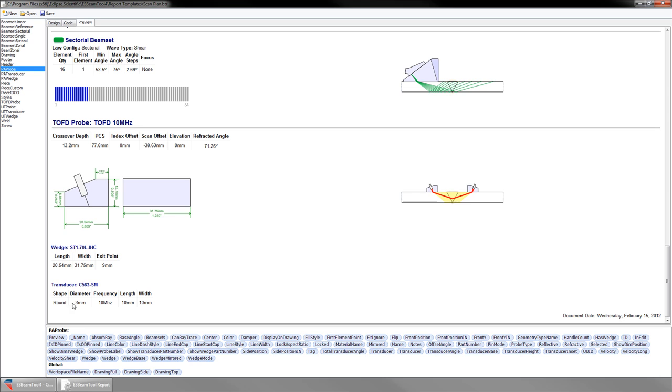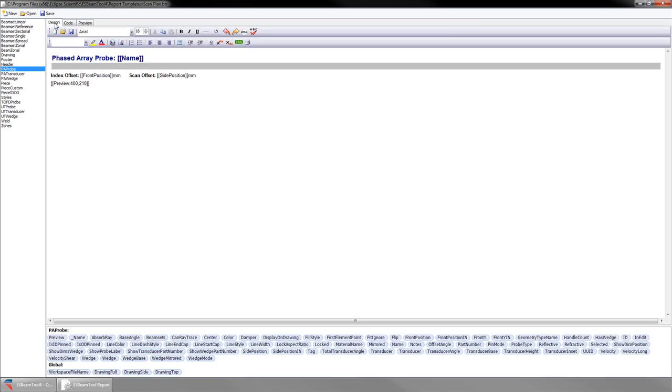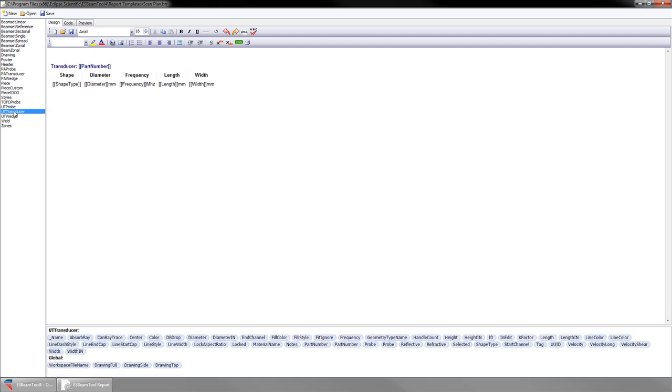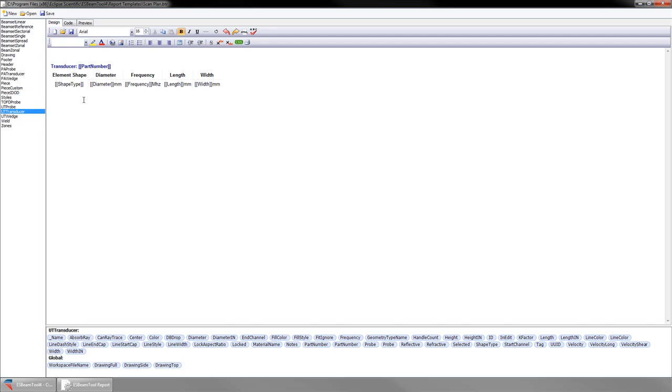Looking at the TOFD transducer, I would like these table headings to be more specific. Going back into design mode, select UT transducers from the report section, and add element to these table headings. Go back into preview and check the changes made.